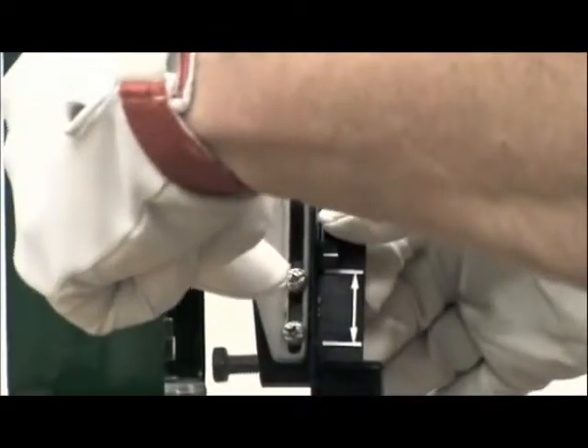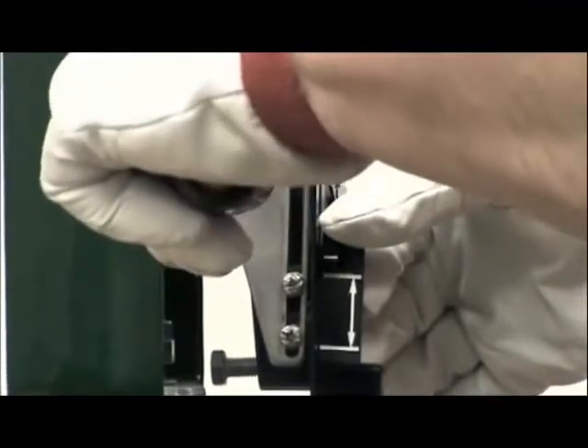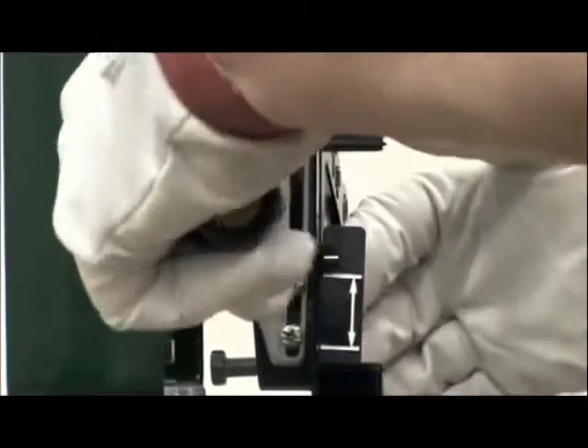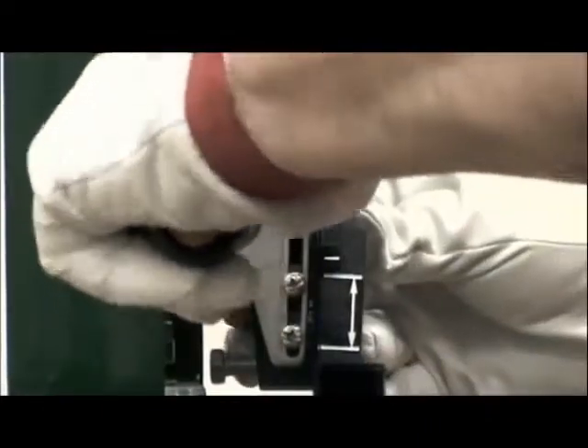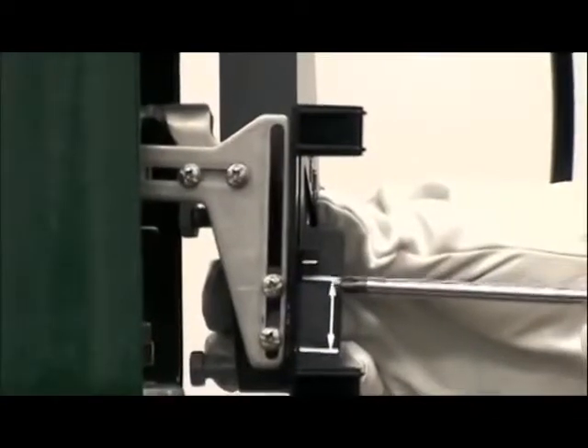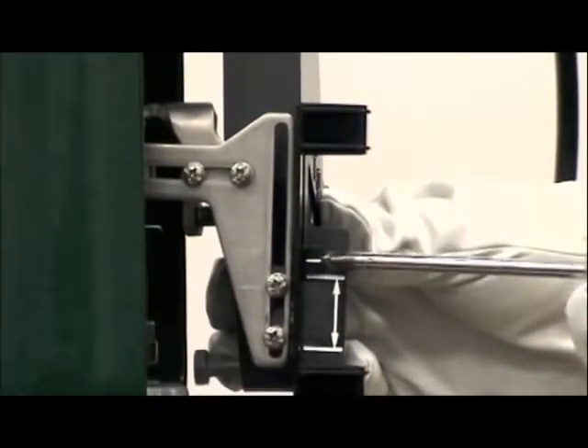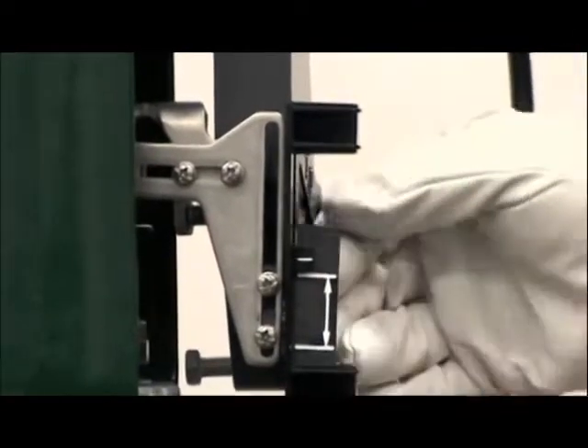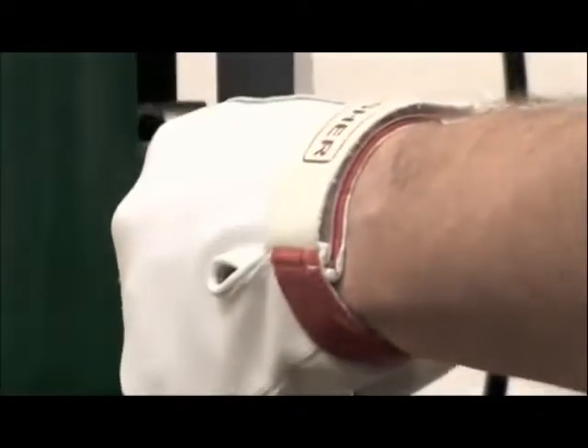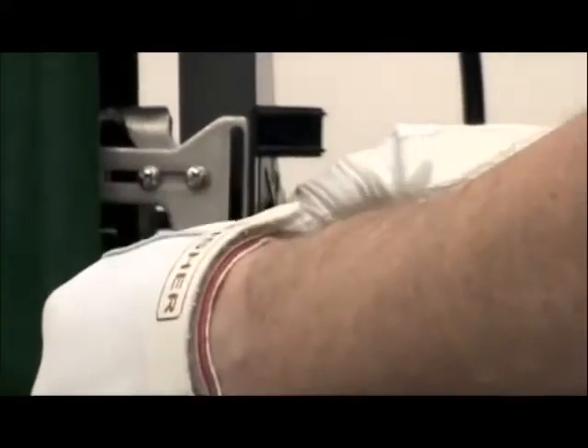Next, we'll bring the extension arm and bring it right to the back of the template. Notice I'm not forcing the alignment template forward. It's nice and flush with the mounting bracket. Now what I want to do is make sure the bottom white line in the array is adjusted above the white line on the adjustment template per the drawing on the template. I'm going to loosen these two screws and move the array into the proper location.